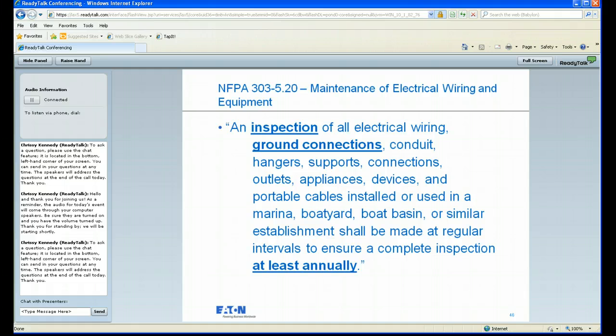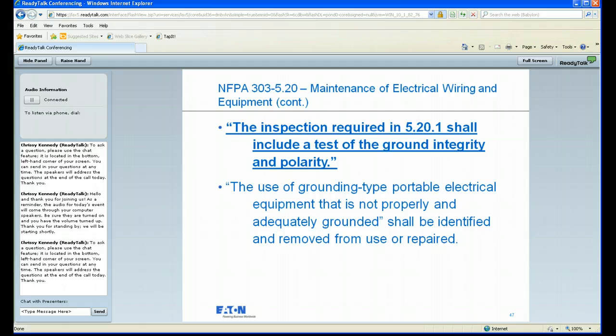An inspection of all electrical wiring, ground connections, conduit, hangers, supports, connections, outlets, appliances, devices, and portable cables installed or used in a marina, boat yard, boat basin, or similar establishment shall be made at regular intervals to ensure a complete inspection at least annually. Basically, this is required for any marina owner or operator to do this at least once a year.